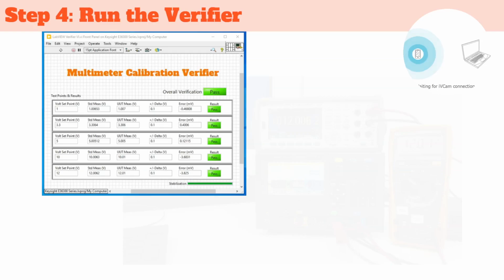So it runs through them. You basically have all these set points set in place in the first place, and then you would run them all together. So when you run them, it goes one after the other, and when it goes through that, it just asks for each specific verifier and each specific set point, and it verifies whether it passes or fails.